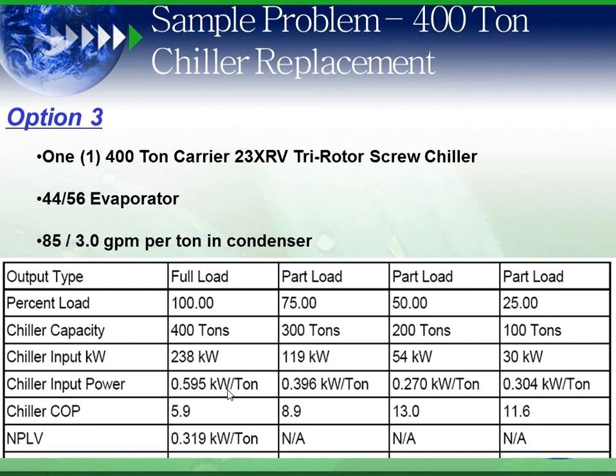Option 3 would be a 23XRV. One of the things that's great about this product is you could change out heads in the field. So let's say today this is a 2-pass chiller that I put in. Maybe when I change out that second machine later on in 2013, I order that as a single pass, and I buy single pass nozzles for the machine, a 23XRV, and I do a series counterflow. In this case, I didn't do that analysis, but that is an option when you're looking at 23XRVs and changeouts, because a lot of times they don't have in the budget for changing out both machines. They only have one. Well, you buy the first one, you put it in parallel, knowing that in another year I could change it over to series by changing the heads on the machine itself.